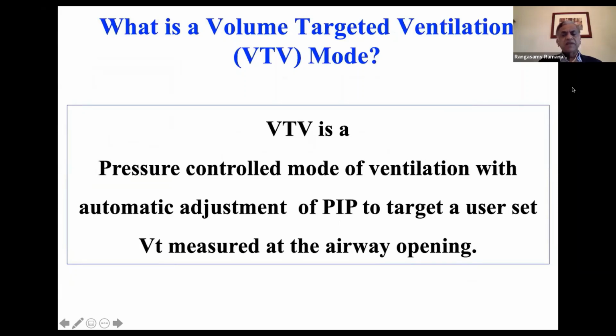So basically, what is a volume controlled ventilation mode? It is a pressure controlled mode of ventilation with automatic adjustment of the PIP to target a set tidal volume that's set by you at the airway opening, not at the ventilator, but at the airway opening.